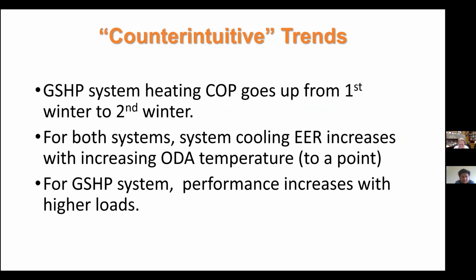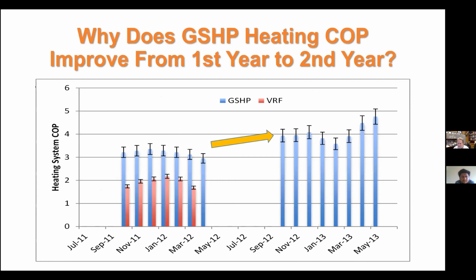So we've got somewhat, I call them, counterintuitive trends. First of all, the ground source heat pump system heating COP goes up from one winter to the next, even though if you look back to the source temperatures, you see they didn't change very much in the ground loop. We have both systems increasing their cooling EER with increasing outdoor air temperature up to a point, and then they drop a little bit. And certainly for the ground source heat pump system, we can see the performance increasing with higher loads, and I'll come back to that in a minute.